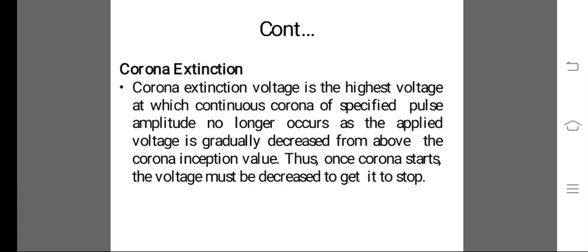Corona Extinction. Corona Extinction voltage is the highest voltage at which continuous corona of specified pulse amplitude no longer occurs, as the applied voltage is gradually decreased from above the corona inception value. Thus, once corona starts, the voltage must be decreased to get it to stop.